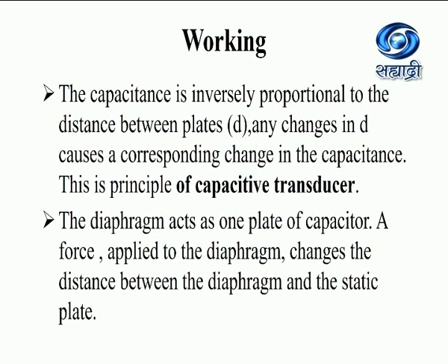The capacitance is inversely proportional to the distance between plates, that is D. So any change in D causes a corresponding change in the capacitance, and this is the principle of the capacitive transducer. The distance between two plates varies with the pressure which is applied to the static plate and diaphragm. The diaphragm acts as one plate of a capacitor. A force applied to that diaphragm changes the distance between the diaphragm and the static plate.